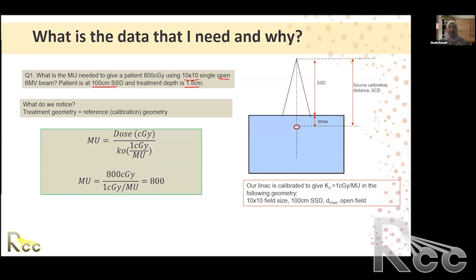And now let's shake it up a little bit. What if the field size is different than 10 by 10? And here's a question. How often do you treat with 10 by 10? You do sometimes, but not very often. Usually you treat with rectangular beams. So in a clinical setup, if you were using a different field size other than 10 by 10, then we need some sort of correction factor relative to 10 by 10. And that correction factor is what we call the total scatter factor, Scp.